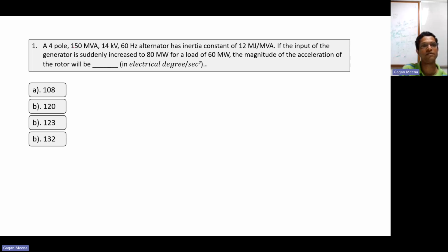A 4-pole, 150 MVA, 14 kV, 60 Hertz alternator has an inertia constant of 12 megajoule per MVA. If the input of the generator is suddenly increased to 80 megawatt for a load of 60 megawatt, we want to find the magnitude of acceleration of the rotor in degrees.